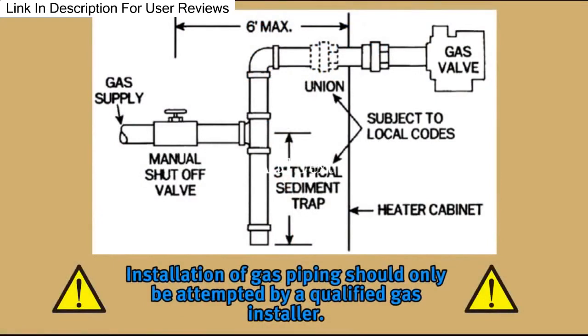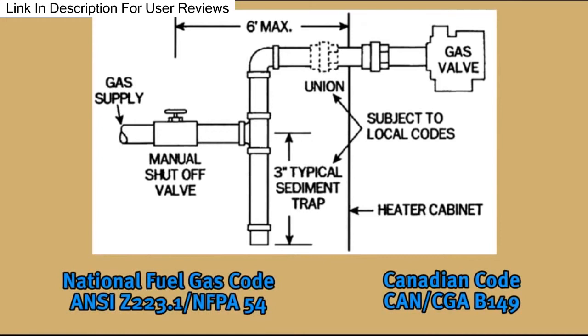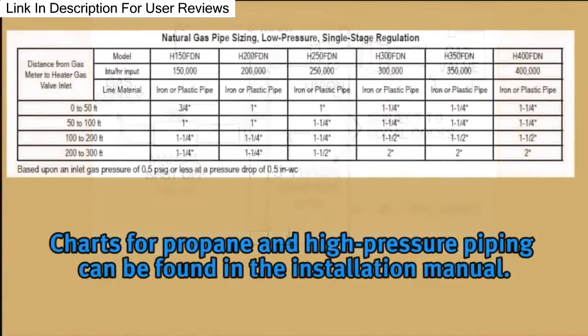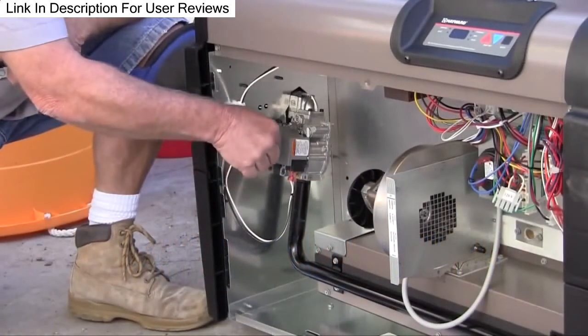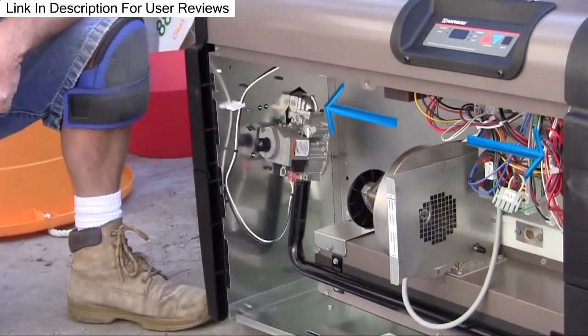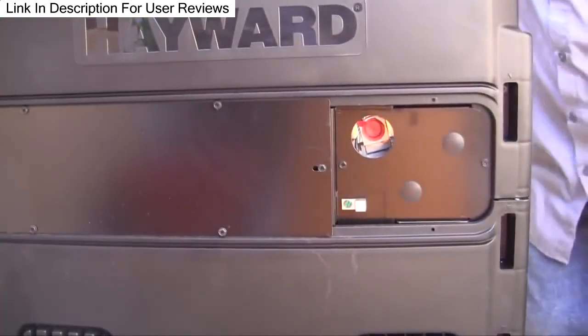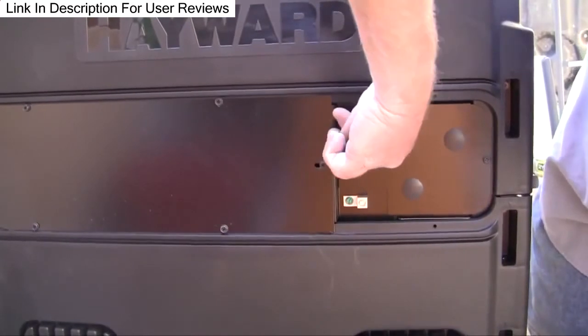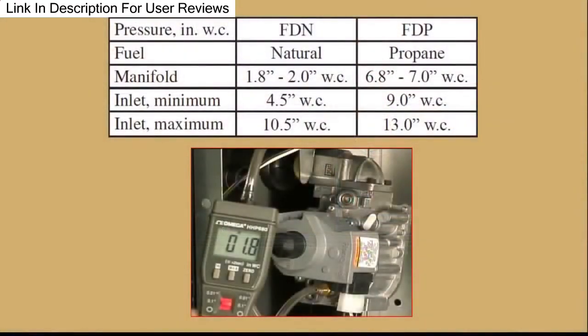Installation of gas piping should only be attempted by a qualified gas installer and should conform to all state and local regulations along with national fuel gas codes and/or the Canadian code. Information on gas pipe sizing and installation can be found in the installation manual. The gas valve is located on the left side of the heater, but gas lines can enter from either side. Be sure to remove the plug from the gas valve before attaching gas piping. Gas pressure should always be checked after installation. Procedures for checking gas pressure are in the installation manual.